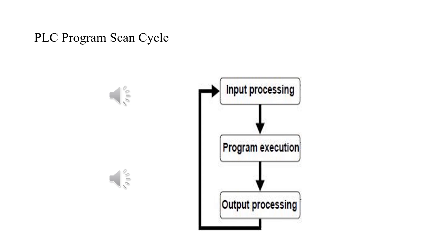Program scan cycles are executed in a duration of milliseconds — one program scan cycle is in the order of tens of milliseconds. If any input device changes its state, it will not be observed until the input processing phase of the next program cycle, which constitutes a latency in reacting to input changes. However, an input device will typically maintain its value for longer than 100 milliseconds, so any change on an input device will not be missed.